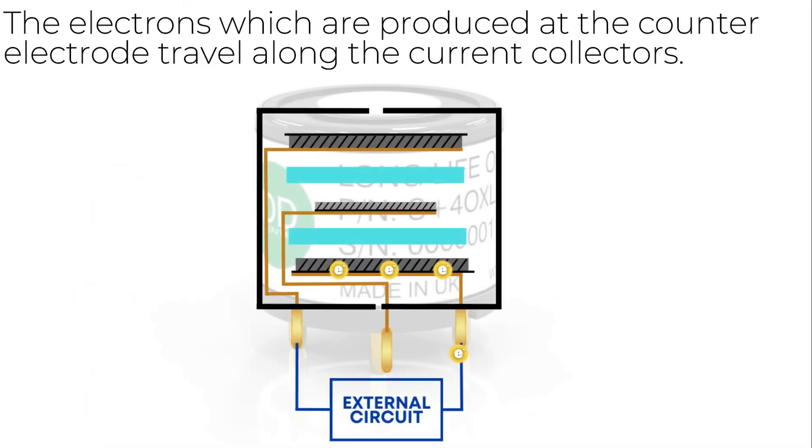The electrons which are produced at the counter electrode are able to travel through the current collector and counter pin into the external circuit and back up to the sensing electrode through the other current collector. There they are available for the sensing electrode reaction.